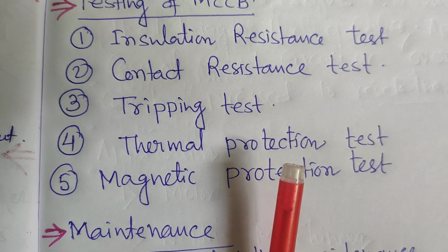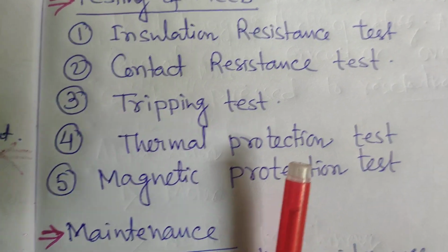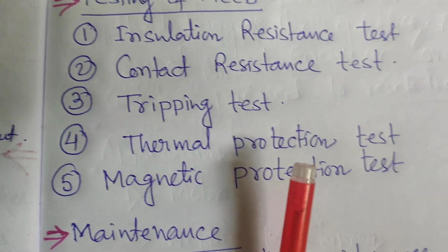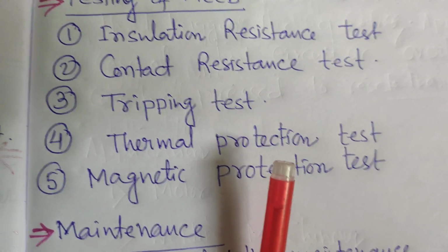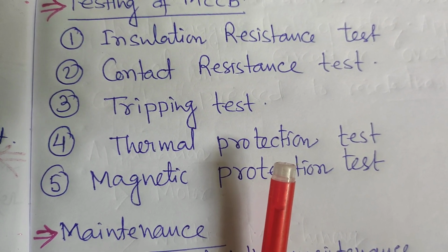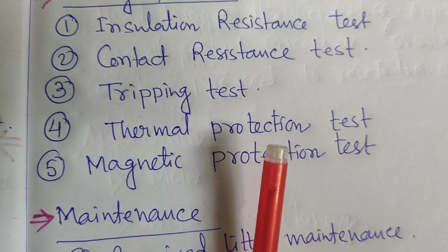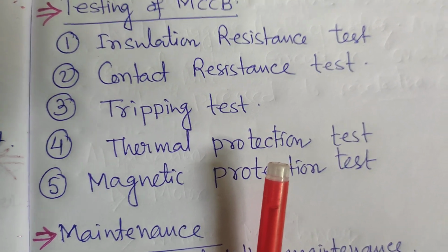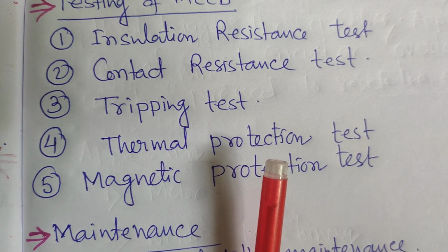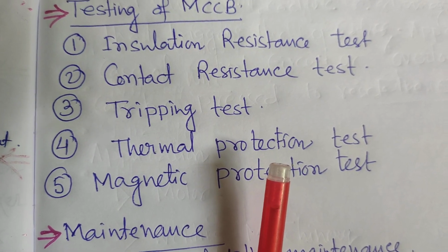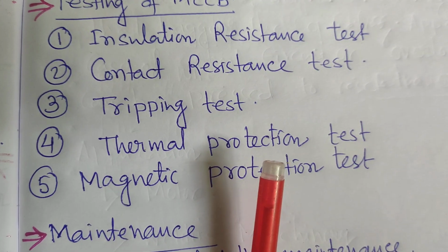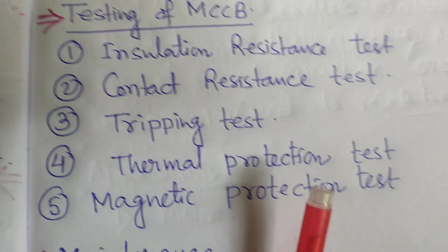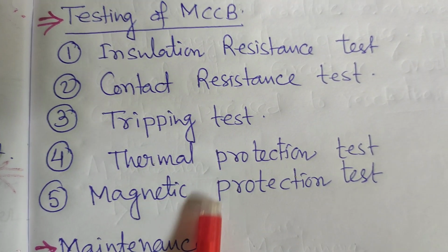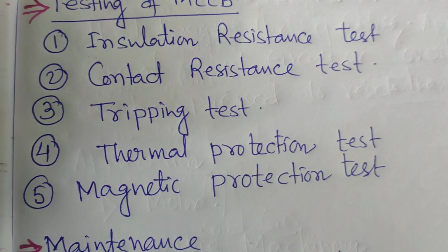And after the fault is removed from the system, if the current becomes normal, then the magnetic solenoid will be deactivated, and if this solenoid is deactivated, then the circuit will be normal, and the contact positions will be the same as before, as the current flows from the input to the output. So these two are the main points of the MCCB you have to remember.